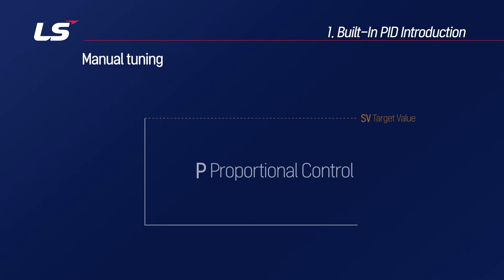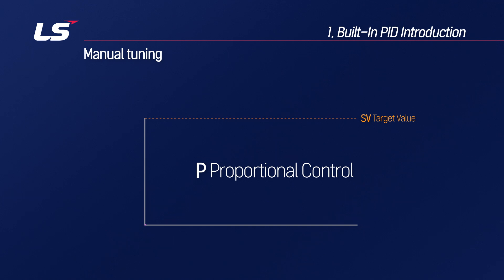Manual tuning checks how quickly the target value can be reached by only adding the P coefficient. When only the P coefficient is included, it is called P proportional control. As PV reaches SV, the error decreases, so the MV value decreases, and it can enter a stable state without reaching the target value.